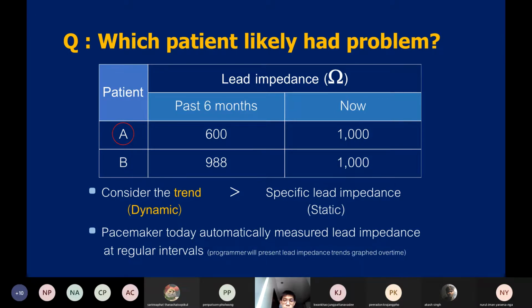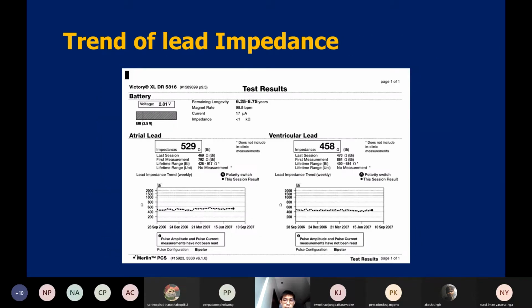Nowadays, the pacemaker usually checks the impedance automatically at regular intervals, so you don't need to put the programmer in and check it yourself. The pacemaker has been programmed to automatically check the impedance, and you would have a graph of impedance over time like this. This is the graph from the pacemaker.